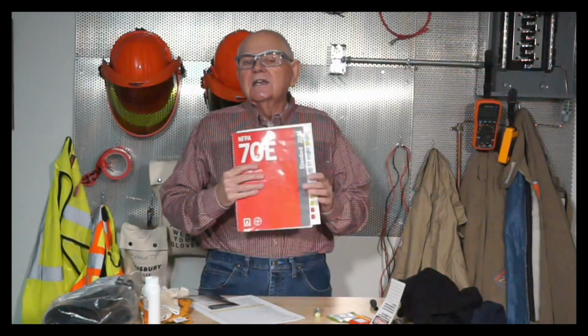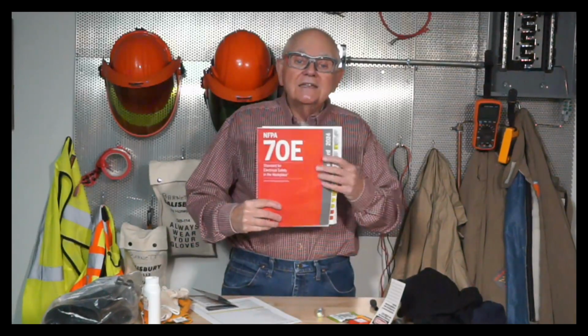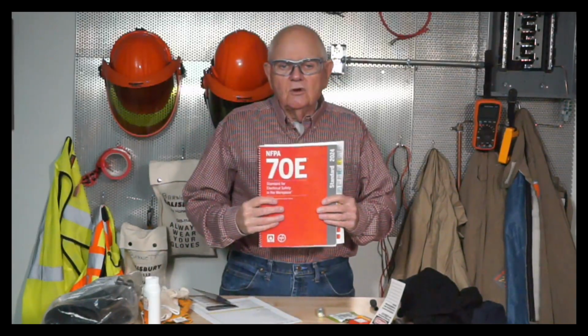The NFPA 70E requirements are based on subpart S of Title 29 of the Code of Federal Regulations, Part 1910, Sections 332 on to 335. And what they cover, that's subpart S, and the way I look at it is OSHA tells us you better comply and you better be safe out there, and here's some tips and guidelines for you, regulations they call them, right? But it's not enough to tell you how to go out there and be safe. So the NFPA 70E standard was written to tell us how to comply with the OSHA requirements in subpart S. So that's why it becomes so important.